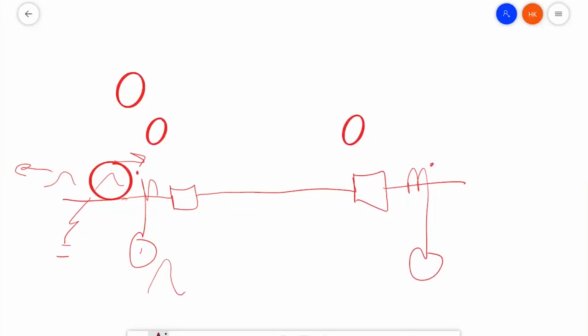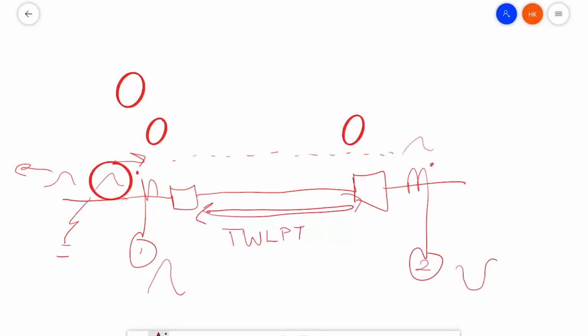Now it's going to travel across the line, and it's going to enter relay number 2. It's going to enter that on the non-polarity side of the CT. So we're going to see this wave in the negative direction. So a good indication that we've got an external fault is that the waves seen by each relay are in the opposite direction. Now the last thing I'll mention here is that what we tell each one of these relays is the time it's going to take the wave to travel across this line. So this time is the traveling wave line propagation time.